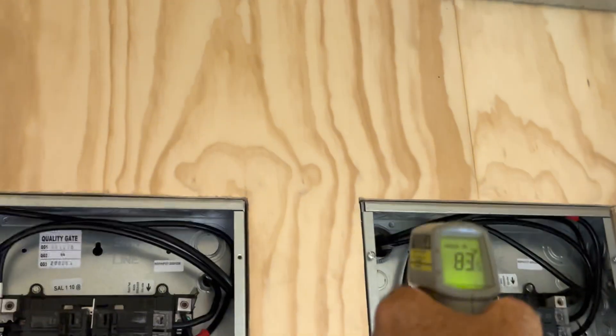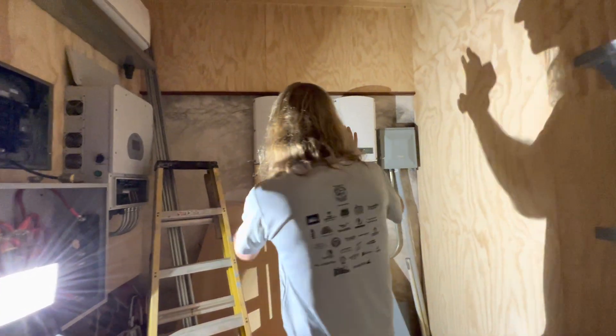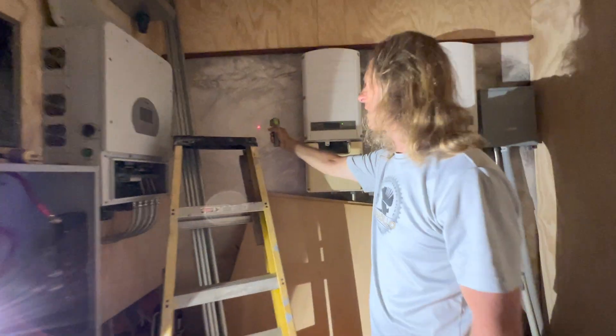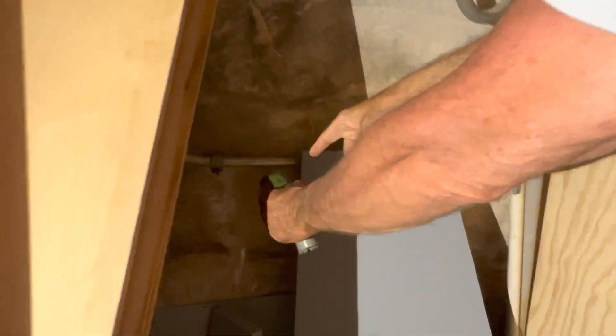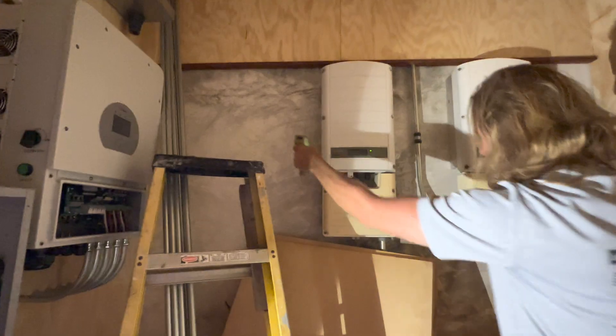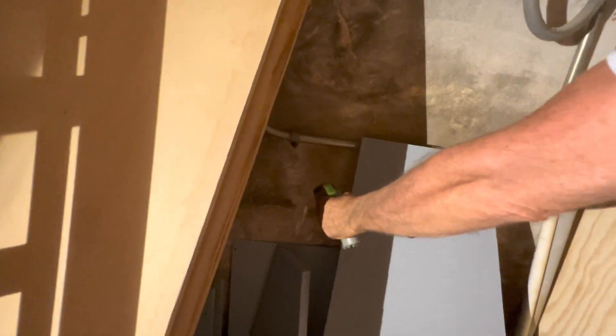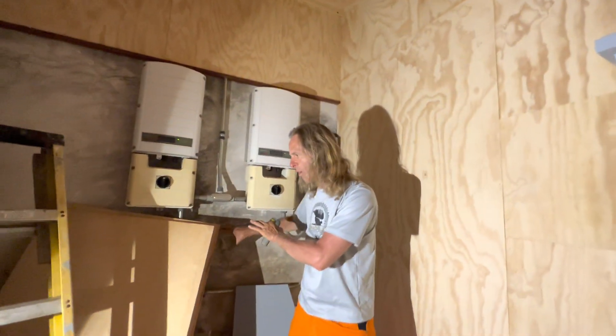So right above that inverter the roof is 90 degrees where the heat is coming up and hitting. The floor is 79 degrees. This temporary wall that all the equipment is mounted to — it's in the middle of the building, off the exterior wall — it's reading 83 degrees. So basically you've got around mid-80s in this room in the middle of the afternoon with these things producing heat full tilt. A concrete wall with rainwater on the other side is 81 degrees, and further down where the water level is, 78 degrees.